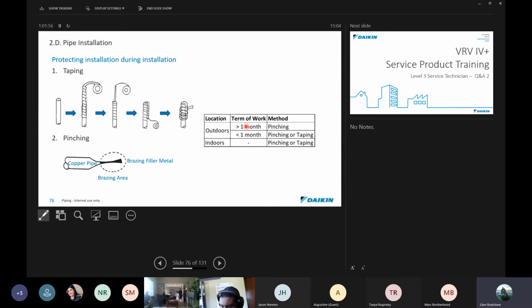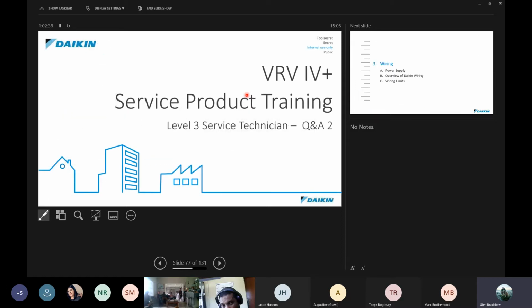And then just a guide over here for when you're taping up pipes, or when working on them outdoors. If it's going to be for longer than a month, pinching; less than a month, pinching or taping; and indoors, pinching or taping. That's because of the environment. You need to consider what's taking place. If you're going to be leaving site, and you look at an installation, some of these residences around Cape Town get done over 2-3 years, then piping should always be pinched and sealed off, because taping will eventually come off in the weather. Insulation tape eventually finds its way off. So that's the end of that section.